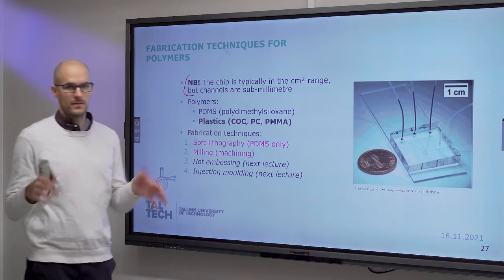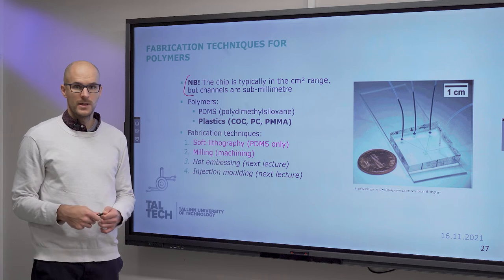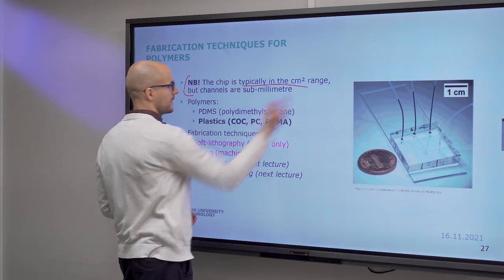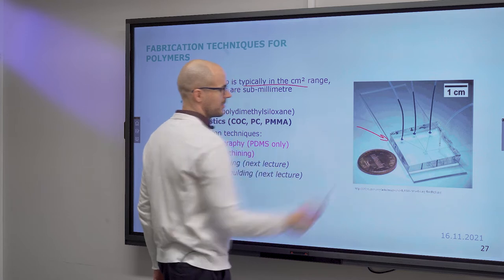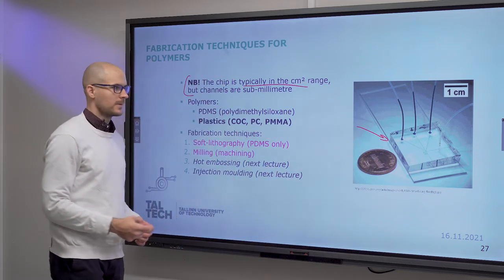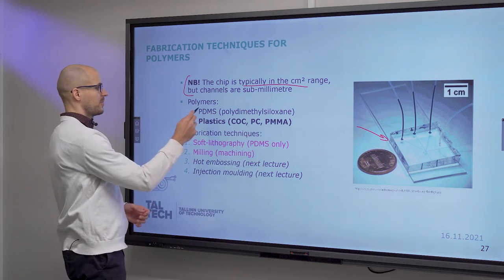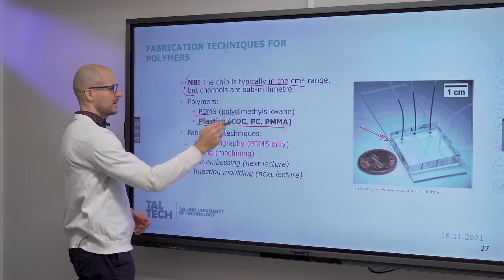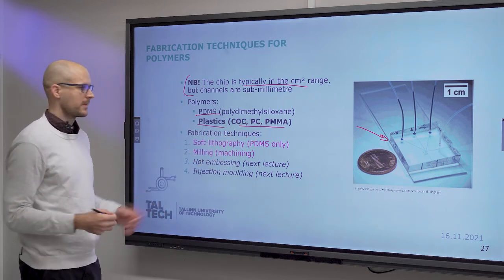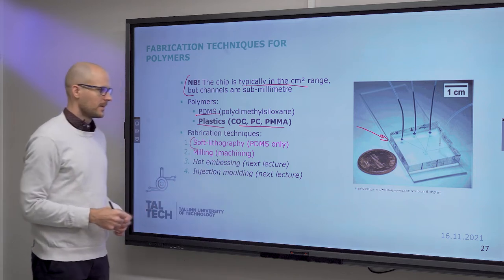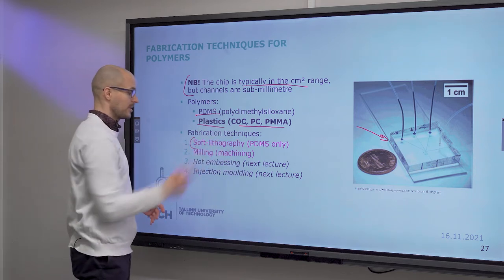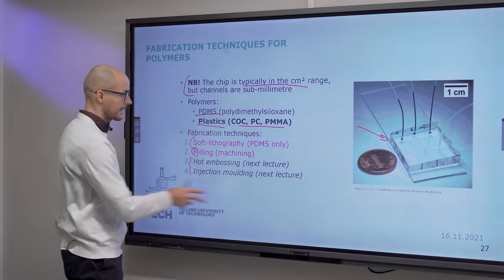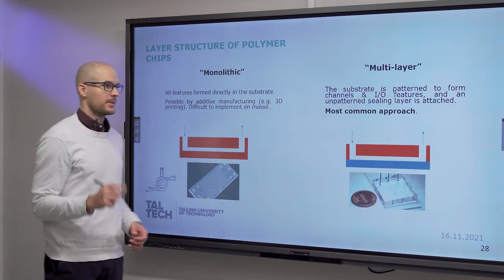So the chip, again, just as a reminder, is in the submillimeter domain. Channels are typically a couple hundred microns across. The chip itself is in the square centimeter range. So this one would be a typical chip size that you see here. Look at the scale. And under polymers, we usually talk about PDMS and plastics. And these are very commonly used plastics. So cyclic olefine co-polymer, polycarbonate, PMMA is acrylic glass or polymethyl methacrylate. Fabrication techniques, soft lithography, we will talk about that. That's only for PDMS. Milling or machining, we talk about that too. The other two things, next lecture. Well, not the next lecture, but the fabrication 2 lecture.